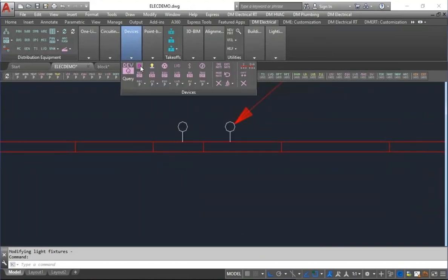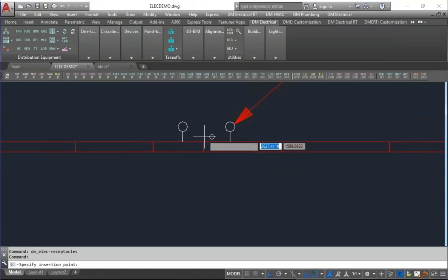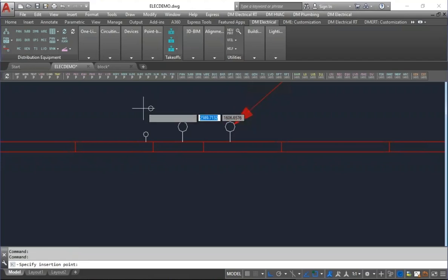If I go and insert another receptacle, it's actually going to be smaller because the receptacle is purely diagrammatic. It's like text. This is counterintuitive, but we want it to be the same size on the printed page, no matter the scale factor. So we actually change the size in the AutoCAD drawing. If the scale factor is twice what it was, we have to make the receptacle half as big. So now we've got a quarter scale receptacle and an eighth scale receptacle.